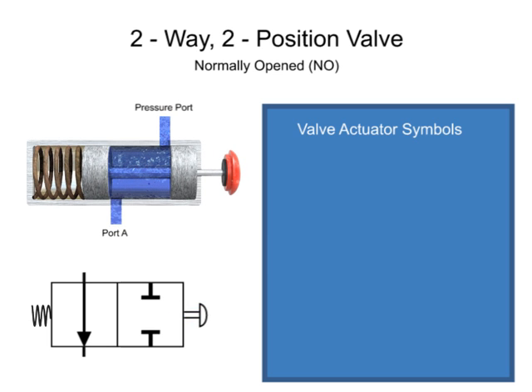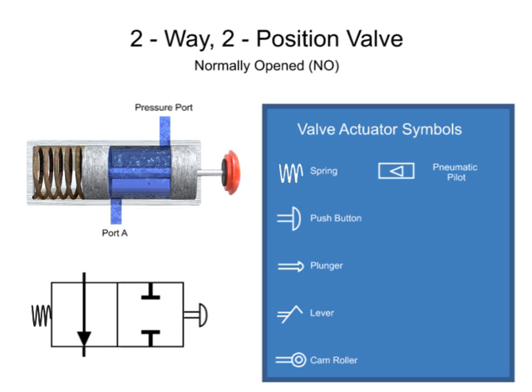Mechanical actuators change valve positions with springs, push buttons, plungers, levers, and cam rollers. Pneumatic pilots change valve position with a pressured air signal. Electric solenoids that change valve positions by directly moving the valve element are called direct solenoids. Electric solenoids that open small pilot valves and allow pressurized air to move the valve element are called solenoid controlled pilot operators.